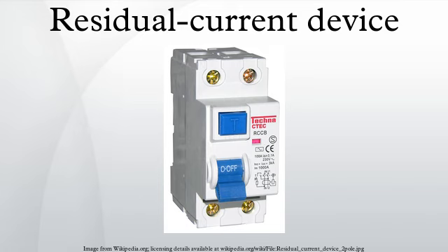To provide some protection with an interrupted neutral, some RCDs and RCBOs are equipped with an auxiliary connection wire that must be connected to the earth busbar of the distribution board. This either enables the device to detect the missing neutral of the supply, causing the device to trip, or provides an alternative supply path for the tripping circuitry, enabling it to continue to function normally in the absence of the supply neutral.